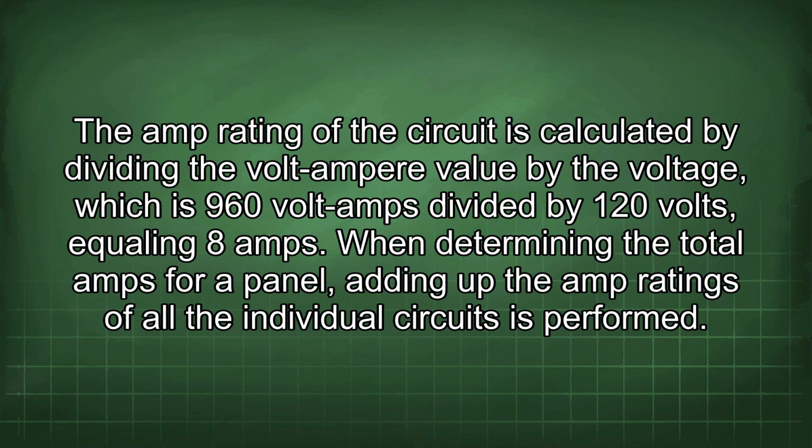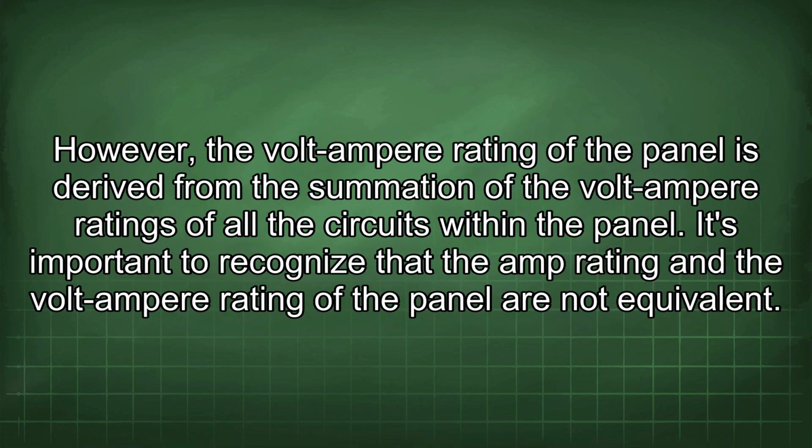When determining the total amps for a panel, you add up the amp ratings of all the individual circuits. However, the volt-ampere rating of the panel is derived from the summation of the volt-ampere ratings of all the circuits within the panel.